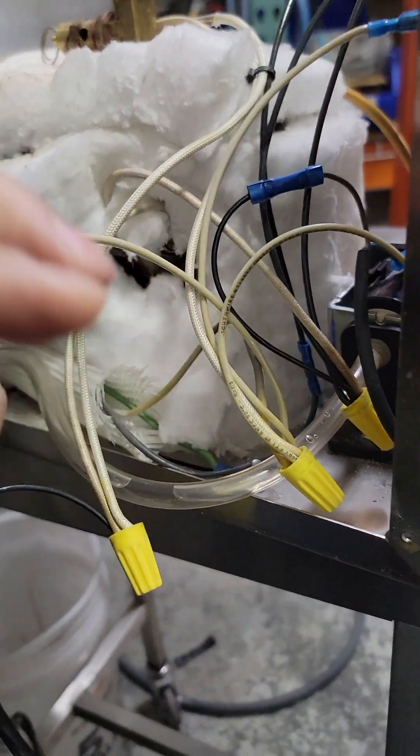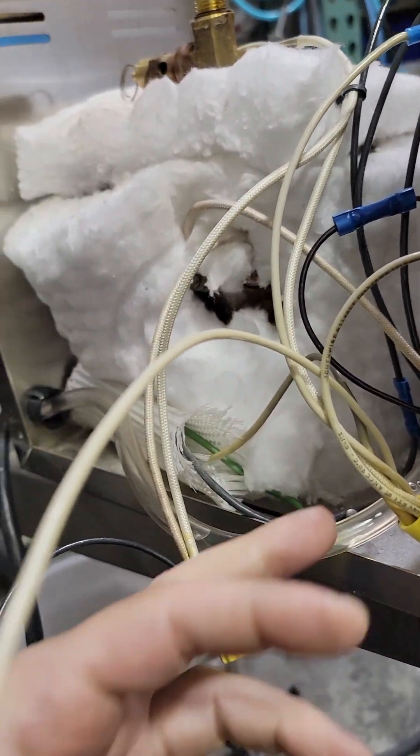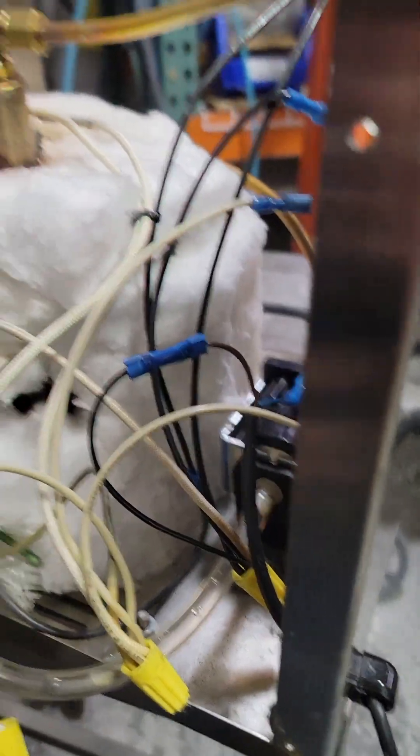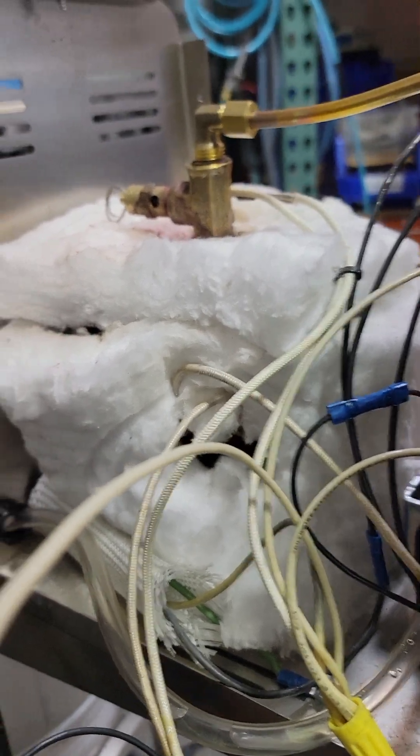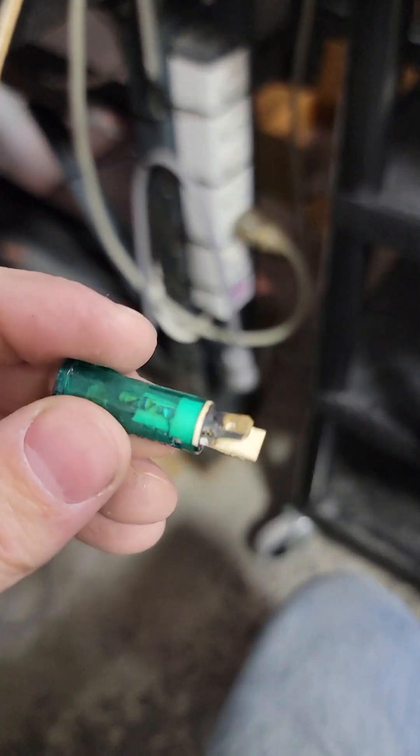Found a whole bunch of things: both lamps burned out, wiring wrong, water pump not working, safety release valve loose. You can see where a clip for one of the lights broke and at some point moved through, hit a contact, and blew it out.